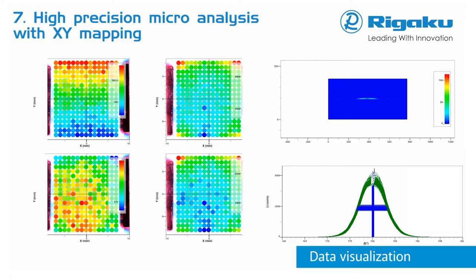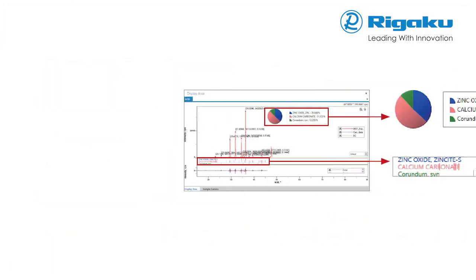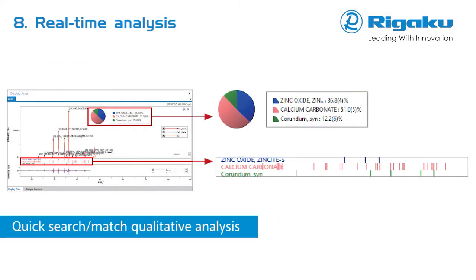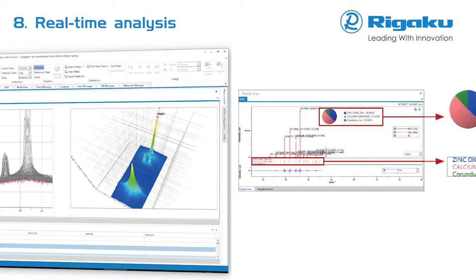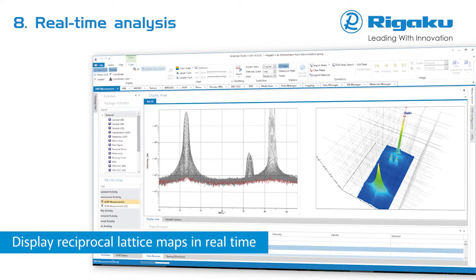Multipoint mapping in the shape of a line, triangle, or rectangular area on an acquired snapshot may be easily set for a mesh measurement. For multipoint measurements, the data visualization plug-in can be employed for communicating the resulting complex information clearly and efficiently via statistical plots and informational graphics. While collecting powder diffraction data, search-match and Rietveld quantification may be performed based on the data accumulated to the current time. The reciprocal space map is displayed in real-time during measurements.